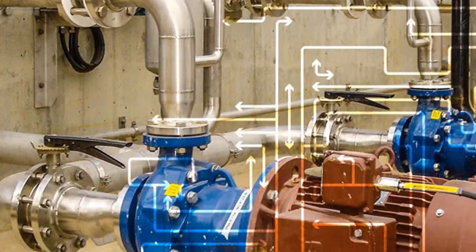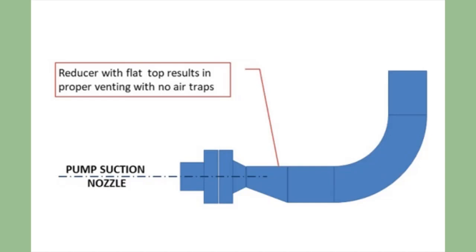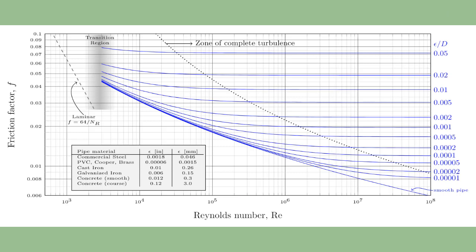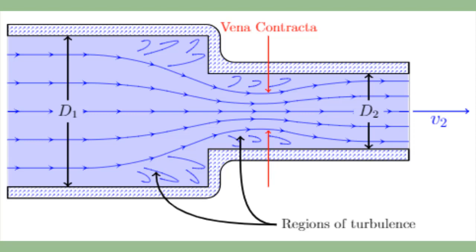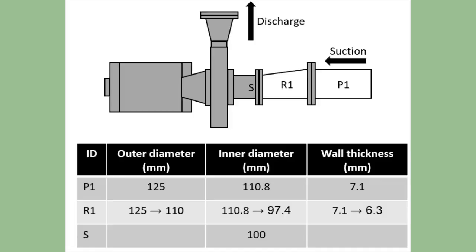Number two, pipe diameter on suction side should be equal or one size larger than pump inlet. Pipe sizing is a balancing act between cost and friction loss. Larger pipes cost more, whereas smaller pipes impose greater friction losses on the system.